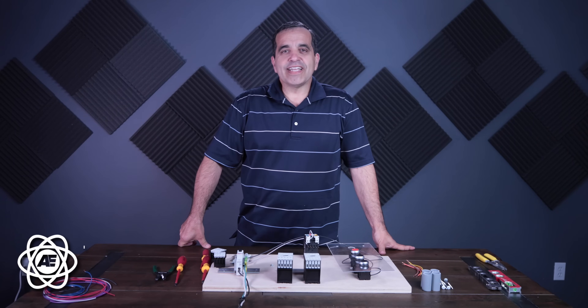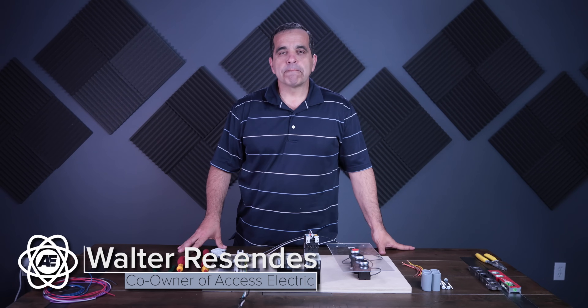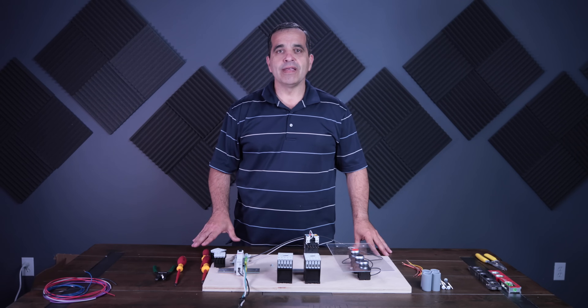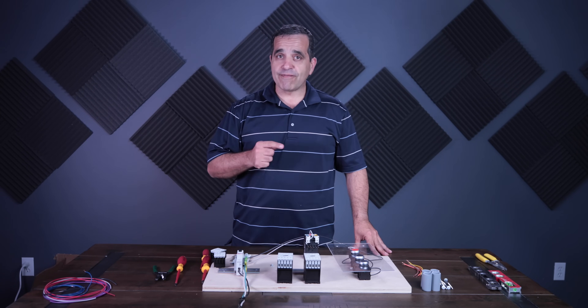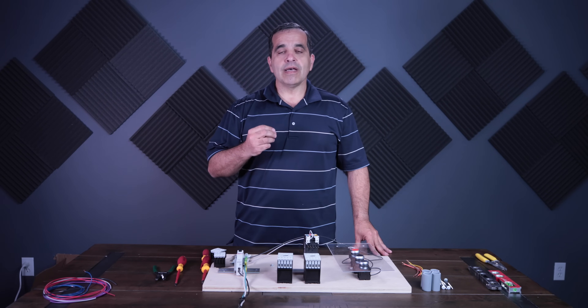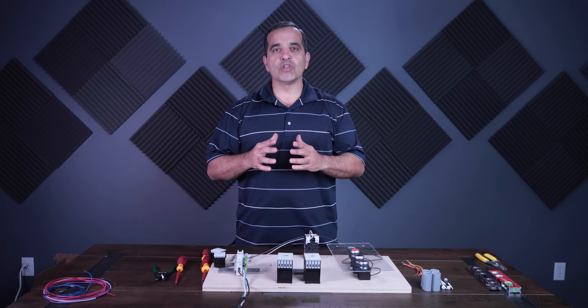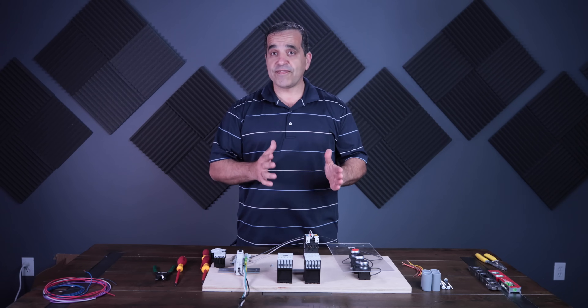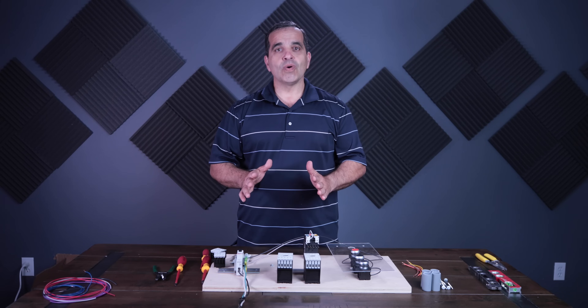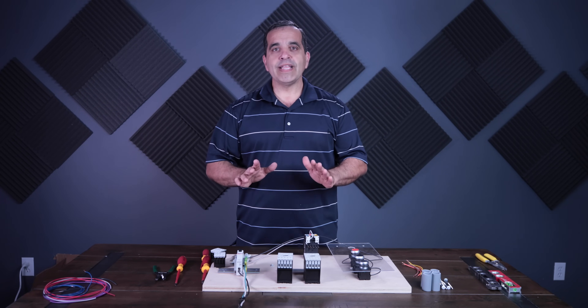Hey everybody, this is Walter with AXS Electric. Today I wanted to go over a forward and reverse motor starter — how do you wire that up so that you can't start both starters at the same time? You're going to need two starters, a forward starter and a reverse starter, and they have to be able to come on but not at the same time. If they come on at the same time, you're going to have a direct short, a phase-to-phase short, which could cause a lot of damage and injury.